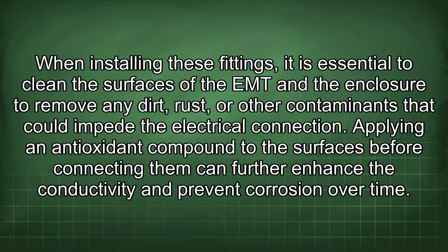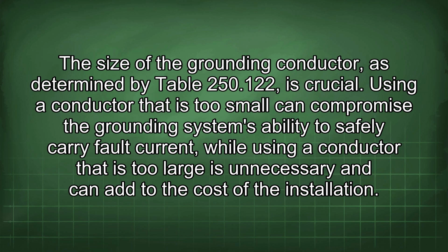When installing these fittings, it is essential to clean the surfaces of the EMT and the enclosure to remove any dirt, rust, or other contaminants that could impede the electrical connection. Applying an antioxidant compound to the surfaces before connecting them can further enhance the conductivity and prevent corrosion over time. The size of the grounding conductor, as determined by Table 250.122, is crucial. Using a conductor that is too small can compromise the grounding system's ability to safely carry fault current, while using a conductor that is too large is unnecessary and can add to the cost of the installation.